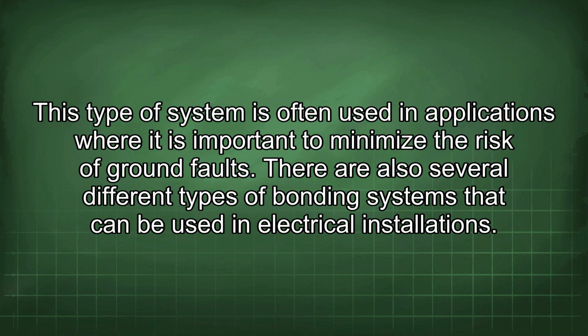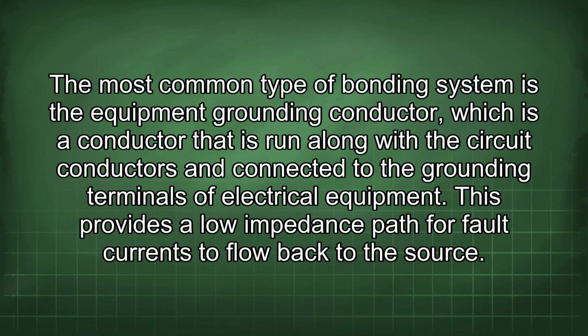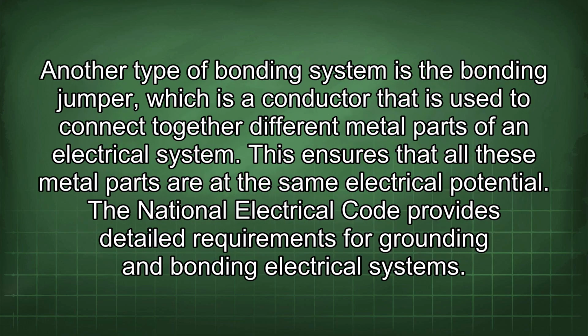There are also several different types of bonding systems that can be used in electrical installations. The most common type of bonding system is the equipment grounding conductor, which is a conductor that is run along with the circuit conductors and connected to the grounding terminals of electrical equipment. This provides a low impedance path for fault currents to flow back to the source. Another type of bonding system is the bonding jumper, which is a conductor that is used to connect together different metal parts of an electrical system. This ensures that all these metal parts are at the same electrical potential.